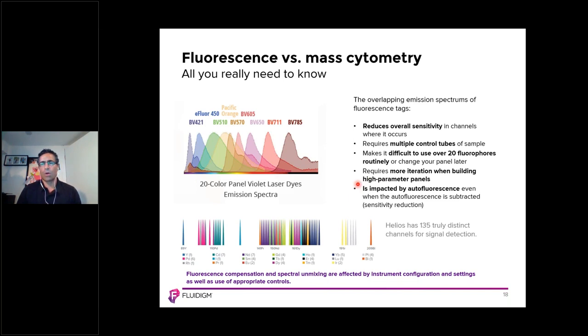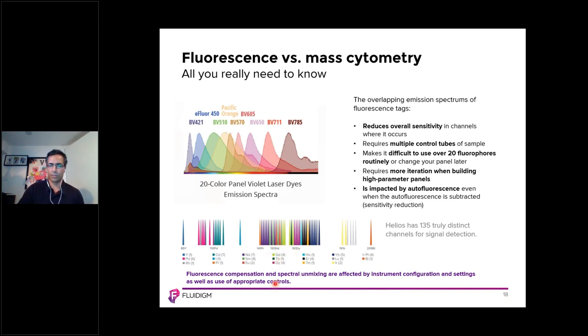In addition, compensation and spectrum unmixing is affected by instrument configuration, settings, as well as the use of appropriate single-stain controls. In contrast, Helios has 135 truly distinct channels for signal detection, which makes high-parameter panel design quite easy compared to flow cytometry. Assay-specific optimization and compensation are not needed in mass cytometry.